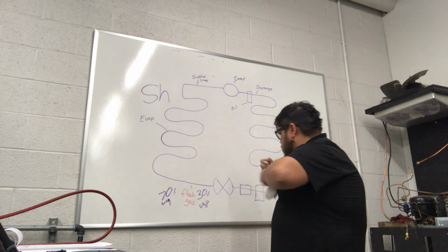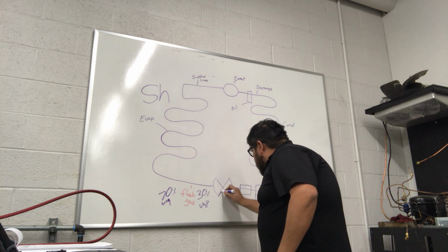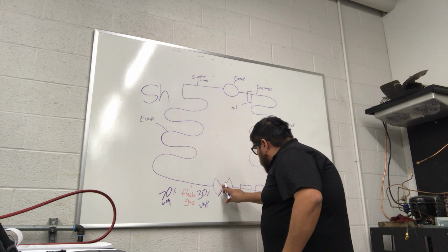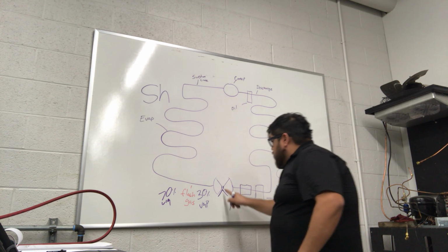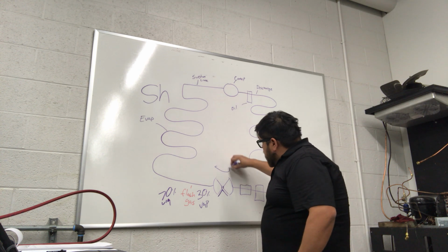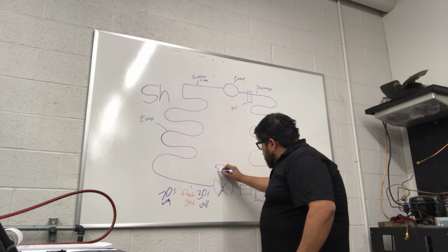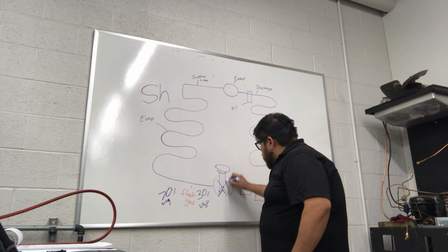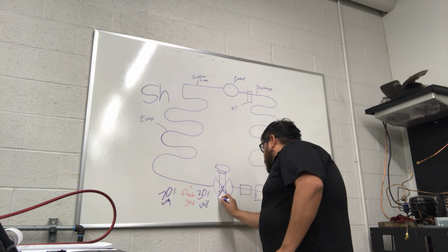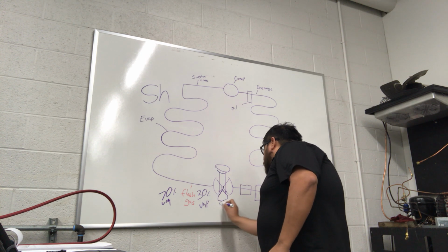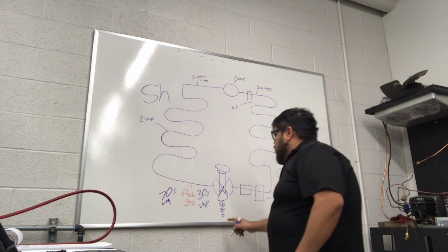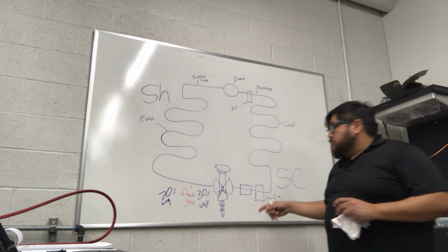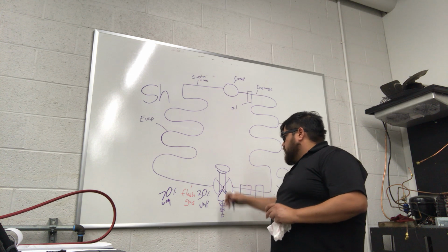So if we were to illustrate this valve, and we use this example that you have up here of a TXV metering device, what you actually have is a cone here and then an opening. And this cone is going to move by the force being applied by the diaphragm. The diaphragm has a bellows that'll push down on this cone, working against a spring. Now, some springs have an adjustment screw on the outside where you could unscrew it and adjust the position of that valve.